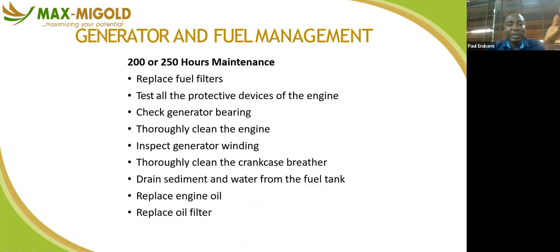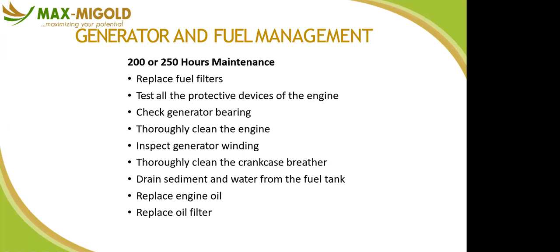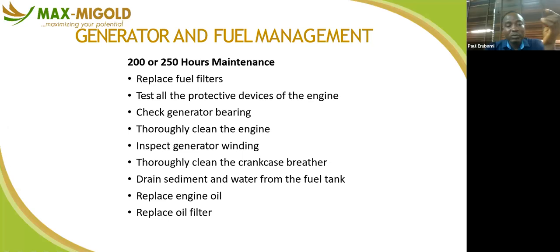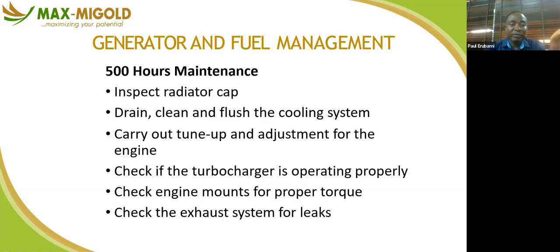So when you are doing your maintenance, some people prefer 200, while some prefer 250. The difference between 250 and 200 is just 50 hours. That's about 2 days if you run your generator 24 hours. So these are the things you replace at this hour: the fuel filter, the oil filter, do all this cleaning, replace engine oil. That's routine maintenance. Then you have the 500 hours maintenance. These are what you do: you change the air filter, and so on, and ensure that these things are adequately carried out.